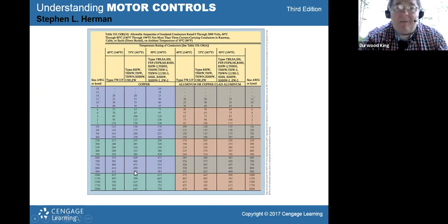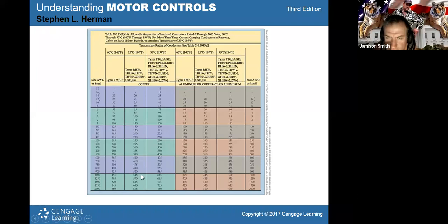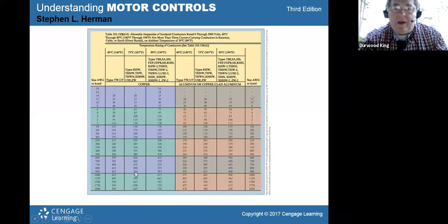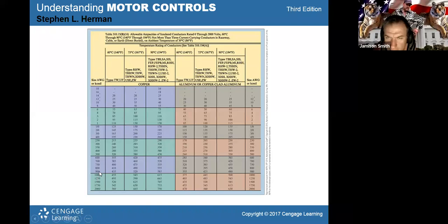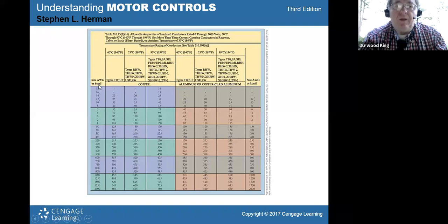So 518 amps, what size wire is it? You've got a 490 amp, a 520 amp. We're talking 500 and, well, okay, which one? Go with the 520. So 520 amp rating here, and what size wire is it? It's 900 kcmil. The k is 1,000, and cmil is circular mil. So it's a 900 kcmil conductor, and again, that's thousands of circular mils.